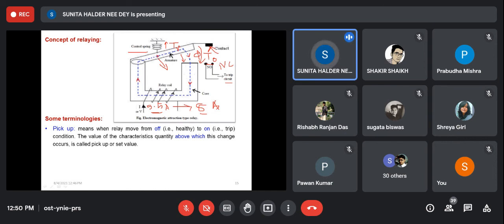That is called pickup. That will happen when the system current is beyond the rated current. Here we cannot set anything. In this type of relay, whenever the relay current exceeds a setting current or system current, obviously the relay will trip, maybe in a slower fashion, maybe in a faster fashion. So this is the simplest relay. Here we cannot control at which current it will operate, and we cannot control the speed of operation either, because it is directly proportional to the exciting current of this magnetic circuit. But it is very easy to understand the concept of pickup from here. So pickup is when the relay starts its operation, and it happens when current goes beyond a certain range.